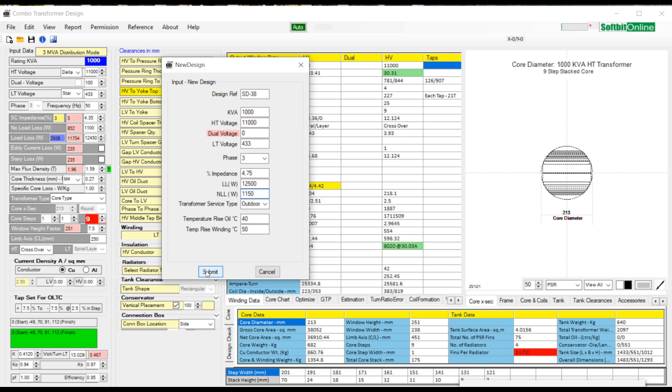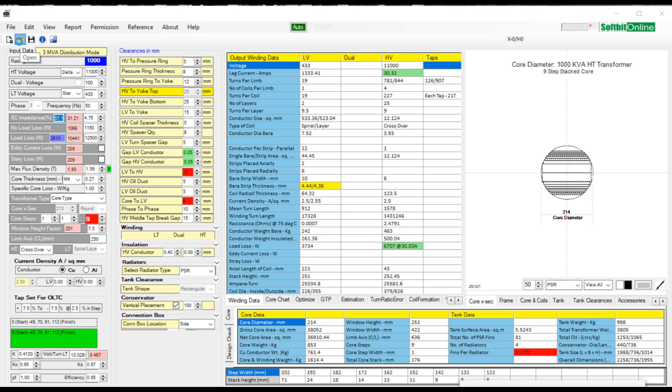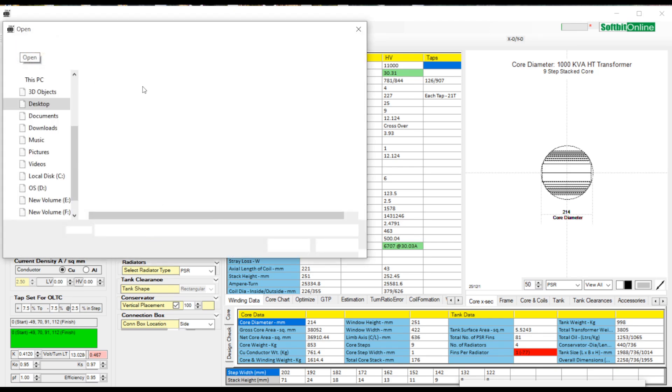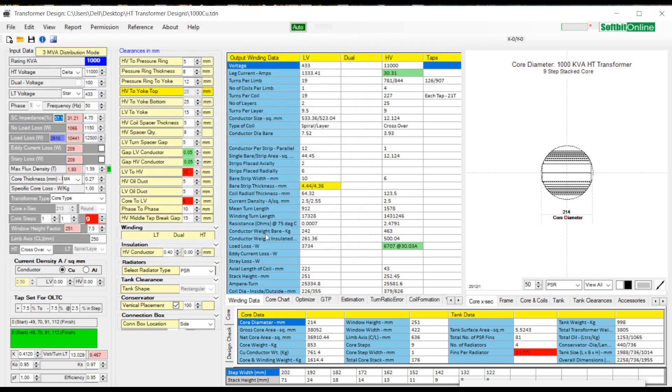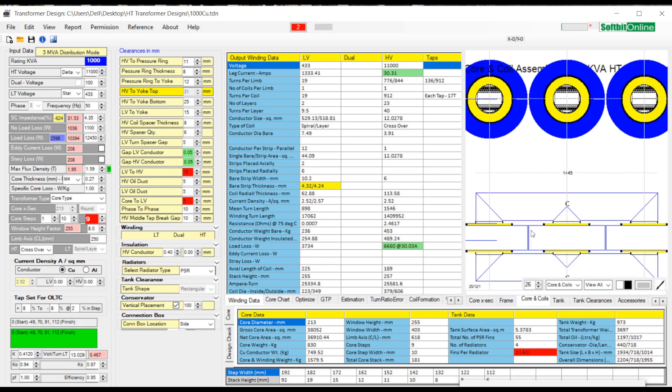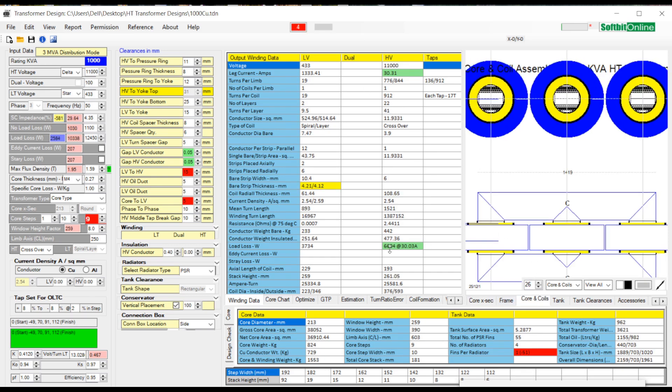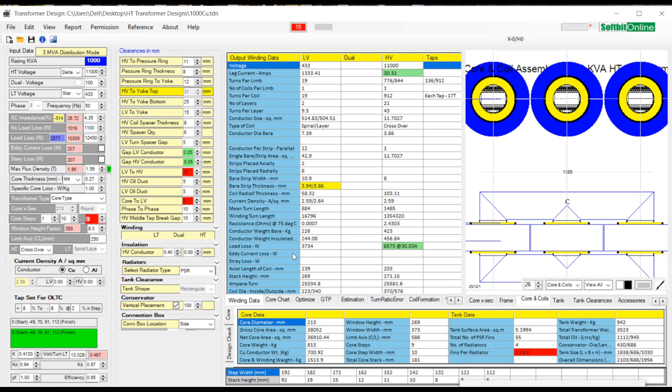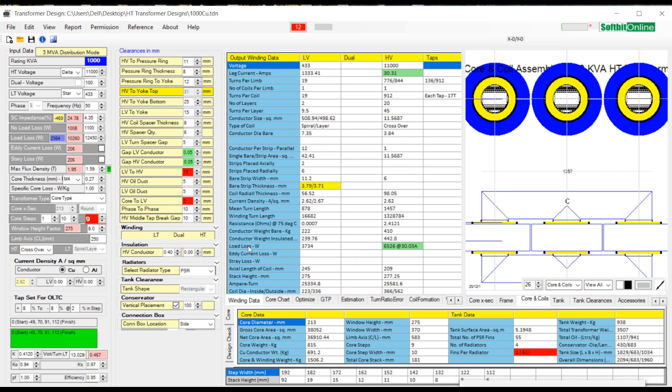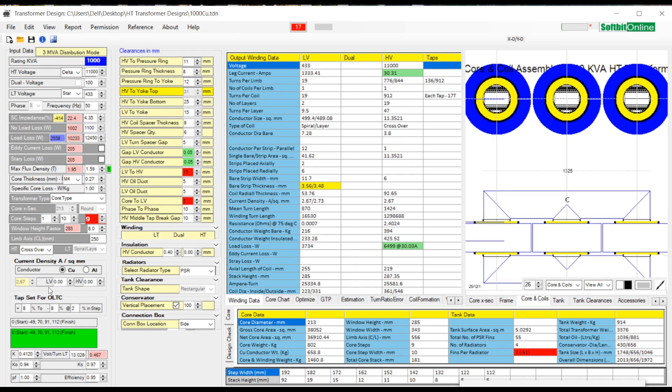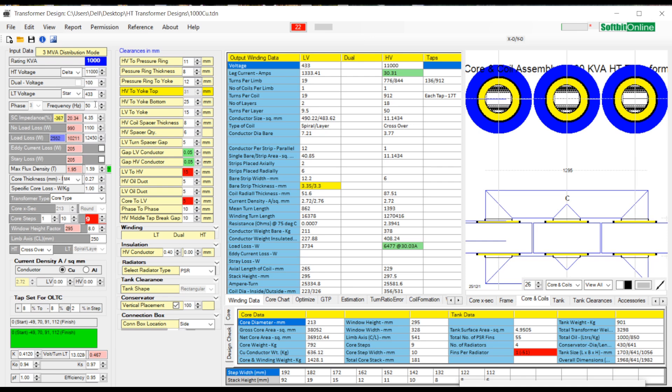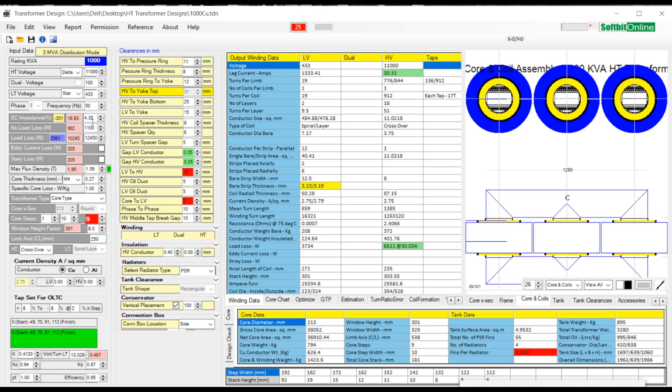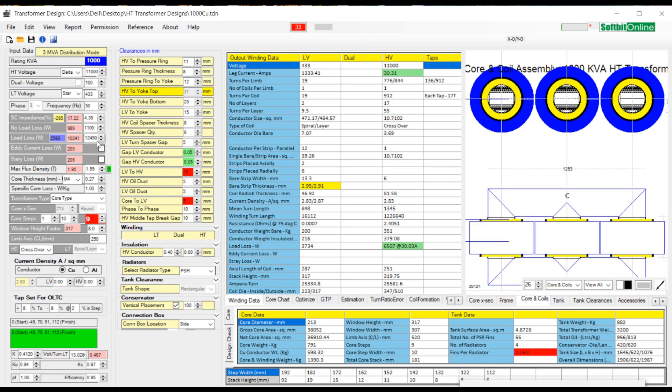Now press submit button to transfer this data to main interface of HT transformer design software. You can see all the parameters transferred to main interface like KVA rating as 1000, HT voltage as 11,000 volts, LT voltage as 433 volts, HT winding connection as delta and LT winding connection as star, percentage impedance as 4.75, no load loss as 1150 watt, and load loss as 12,450 watt.